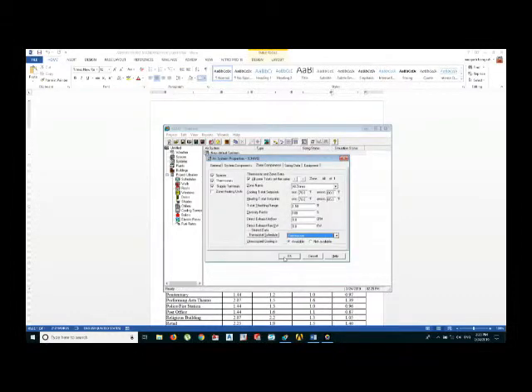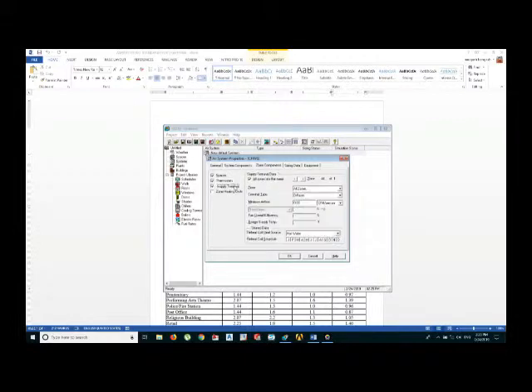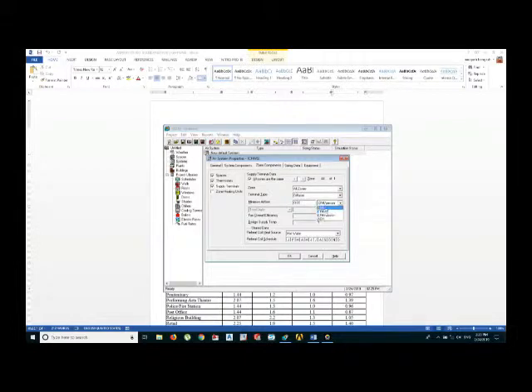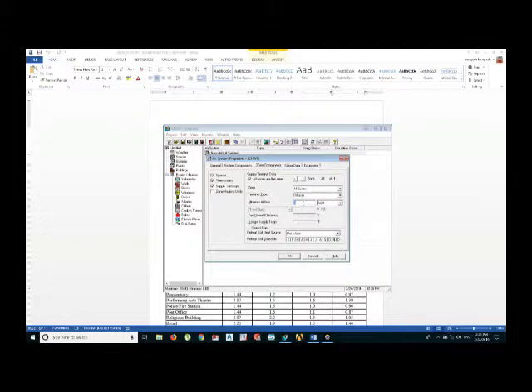Third one is supply terminal. Supply terminal: like how much CFM you need to draw from your diffuser because of the heat. So I'm using the ACH method. So from ASHRAE you can put the ACH of your space - if it is classrooms, office, gym, anything. So I am using six ACH for my office.